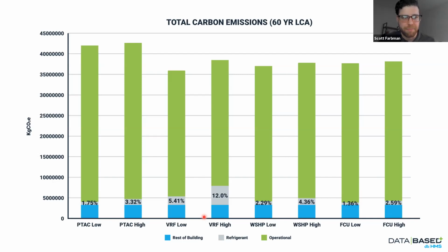I'm not saying we need to stop designing and implementing VRF systems, but what this does tell me is that field fitted and installed installations need to be kept a really close eye on. I think we might need more QA/QC in the field when it comes to VRF buildings to ensure that the leakage rate is as low as possible. This also tells me that with this emerging technology of different refrigerants, if we can continue to use VRF systems, but use a different refrigerant type, we're going to have the best performing system across the board, hands down, because on the operational side, the operational energy is the least amount for the VRF.